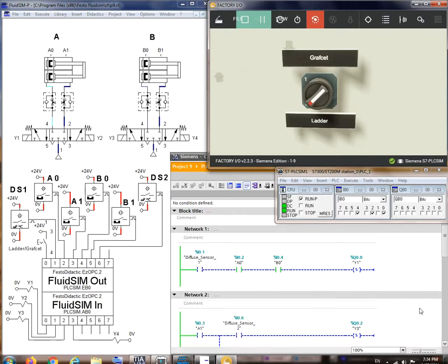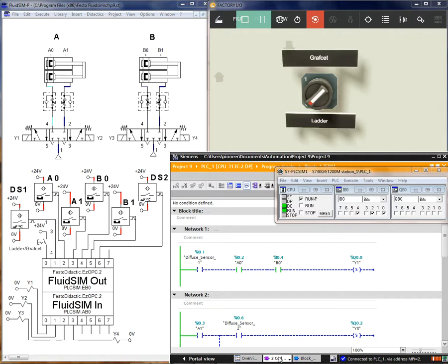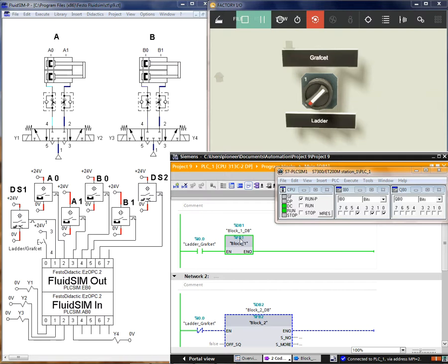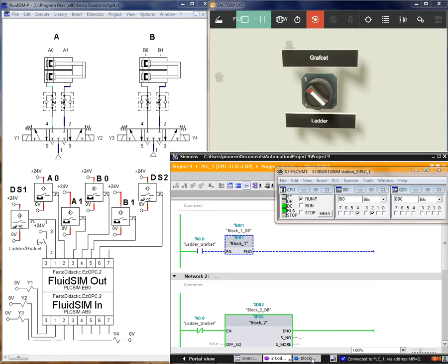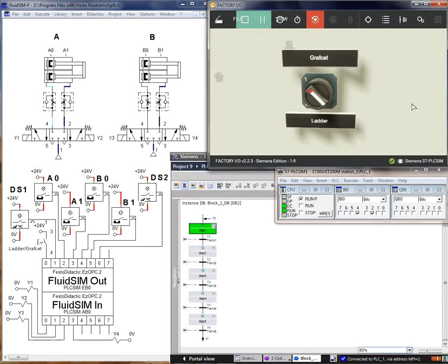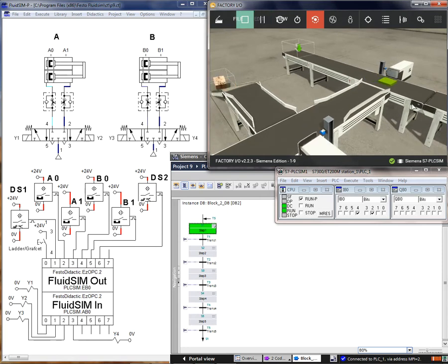I will show you OB1 or Organization Block 1. FB1 is activated, meaning the ladder language is allowed to work. I want to change it to the grafcet mode. Now the grafcet mode is active — I0.0 is deactivated. You can see the colors going blue, meaning FB1 is not allowed to work and FB2 is now active with the grafcet language.